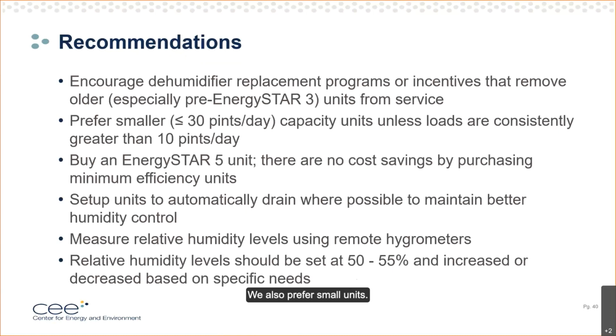We also prefer small units; 30 pint per day or less capacity units can meet the vast majority of loads we encounter in Minnesota basements. We should also remember that dehumidifiers are not great for removing moisture from large, consistent liquid water intrusions, so we point to other solutions in those situations.